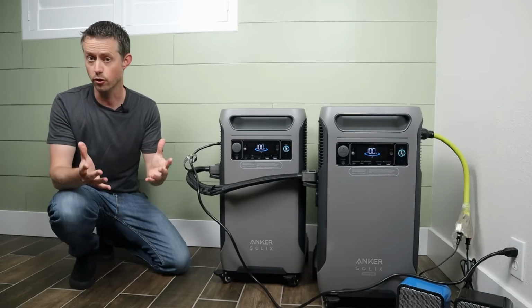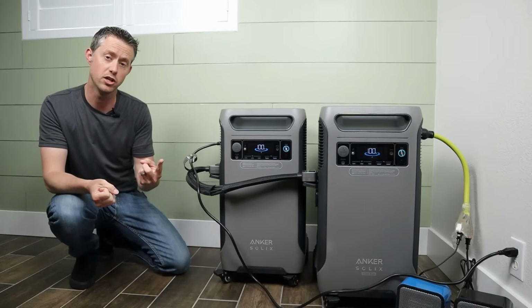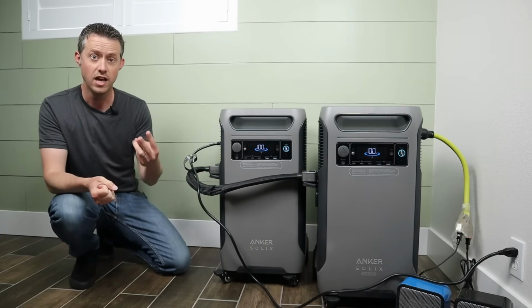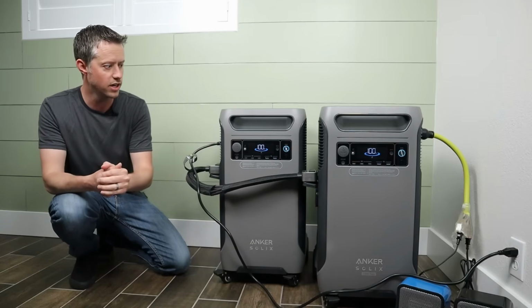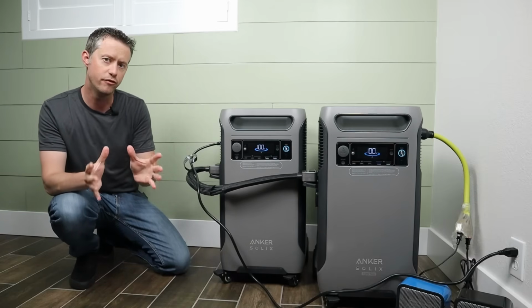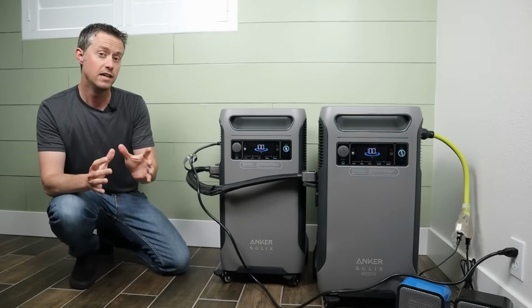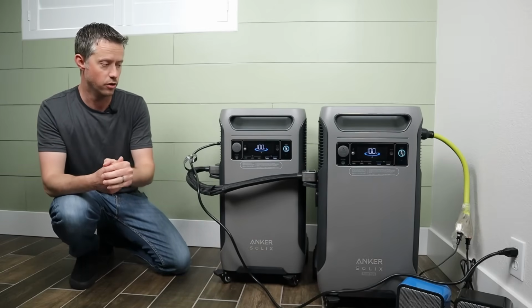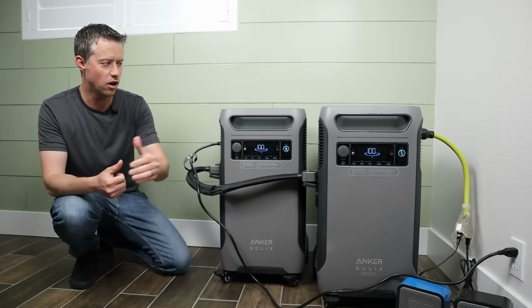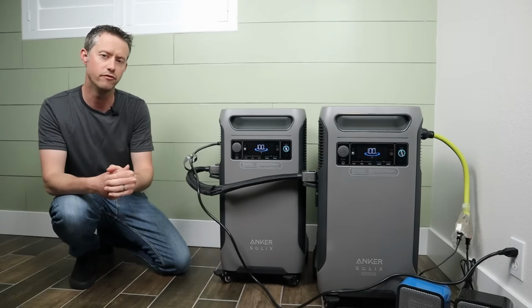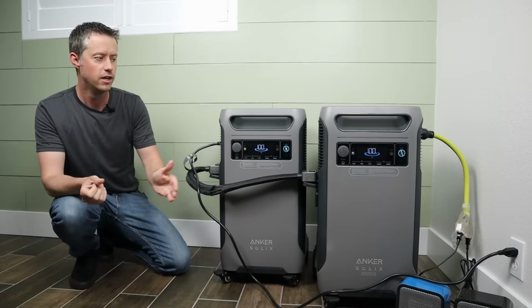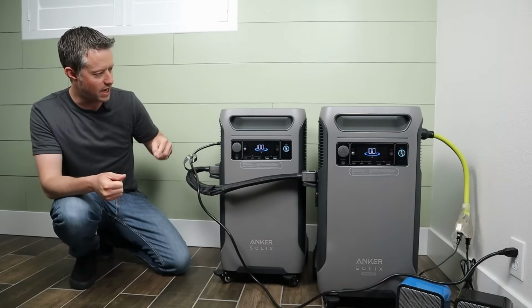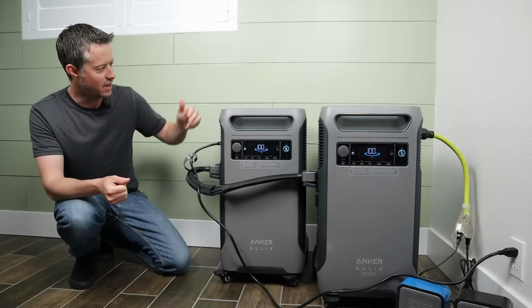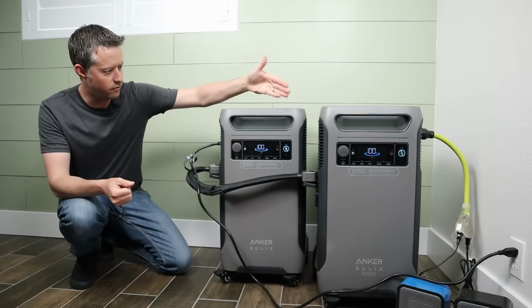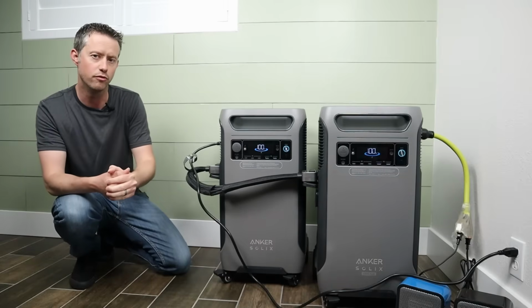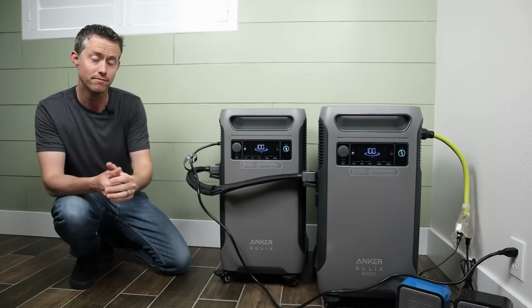Now, I will say with the earlier test that I did with the DIY expansion batteries, the solar charge controllers, and even the Chargeverter or AC charger connected in, as long as you stay under 55.5 volts, the inverter should stay powered on. I did do some extra testing off camera, and when I went above 55.5 volts, it did trigger the inverter to shut off. So maybe that's what's happening here, but since the F3800 is charging the F3800 Plus, you'd think that it wouldn't go over 55.5 volts. I'm not sure.